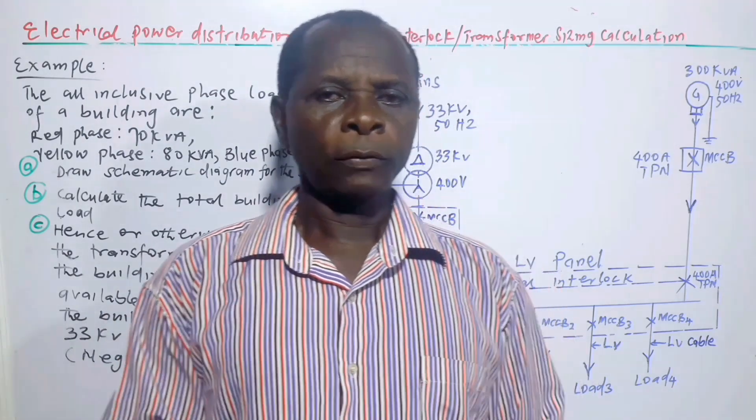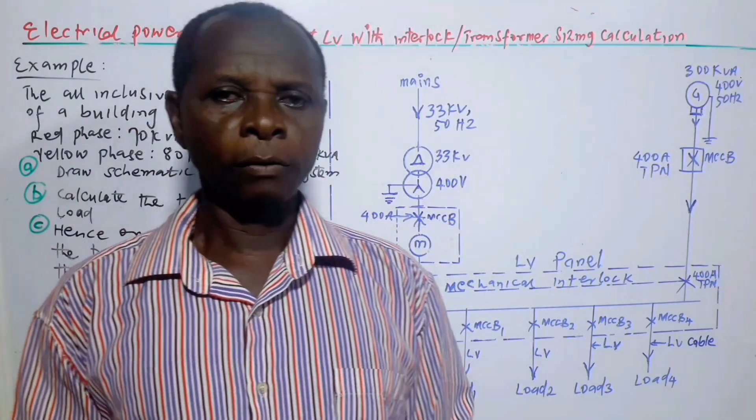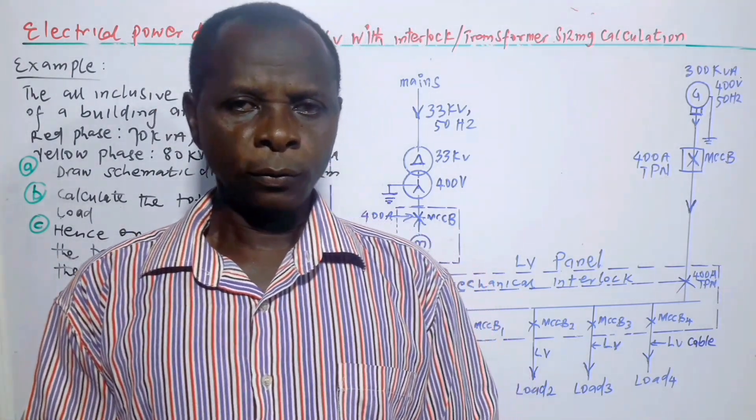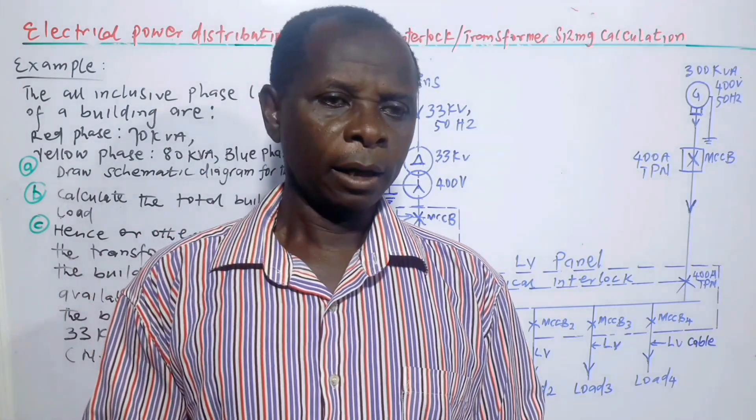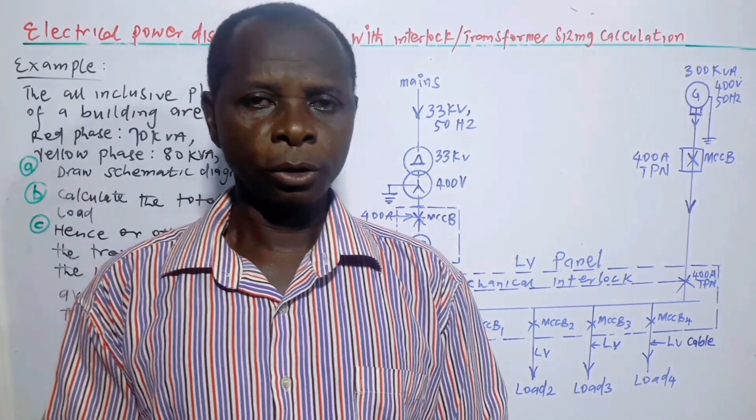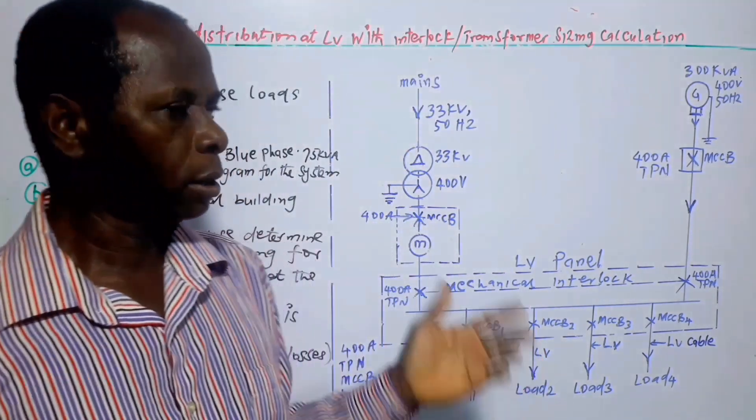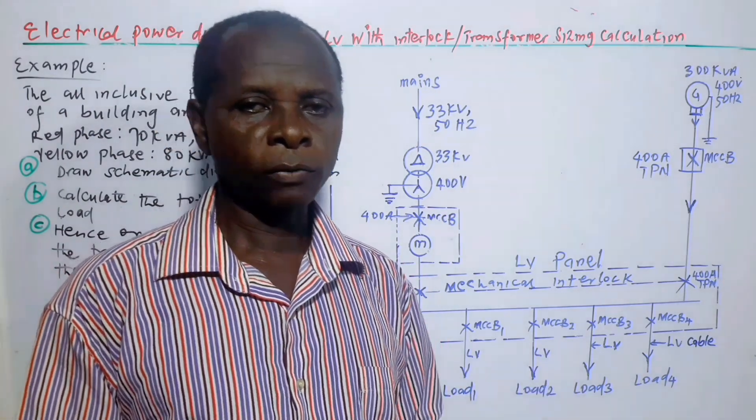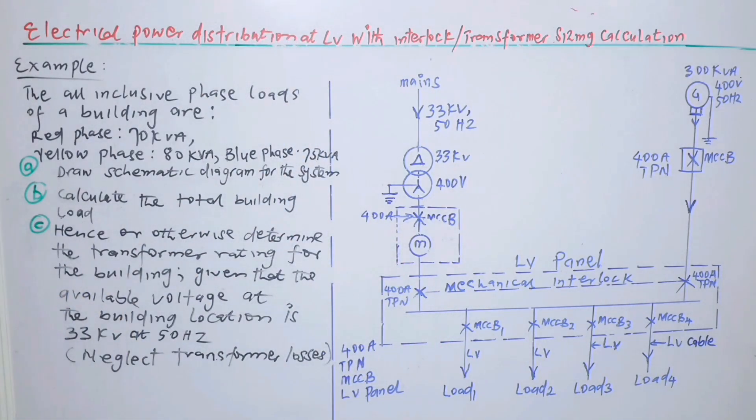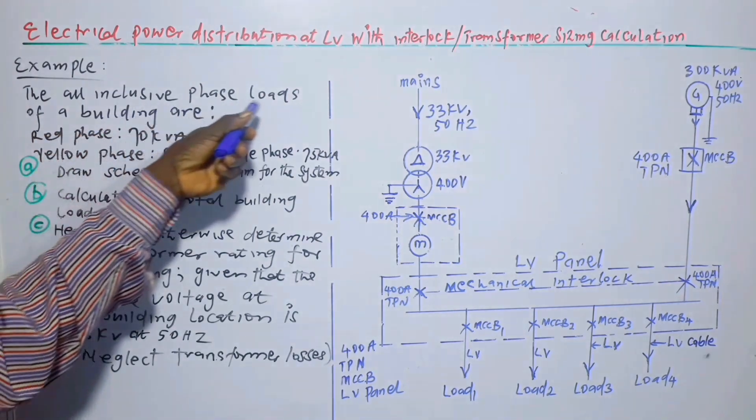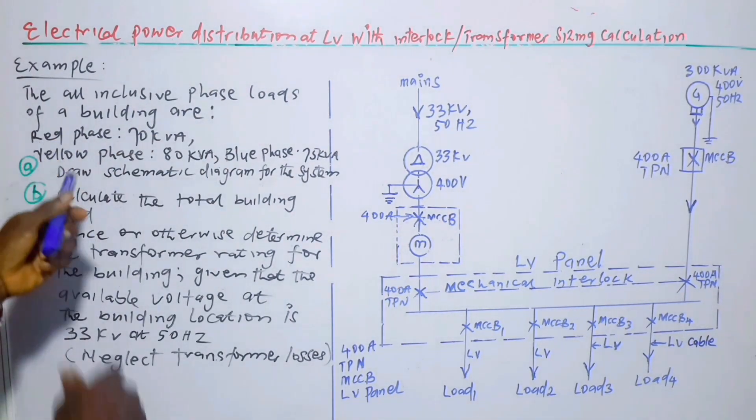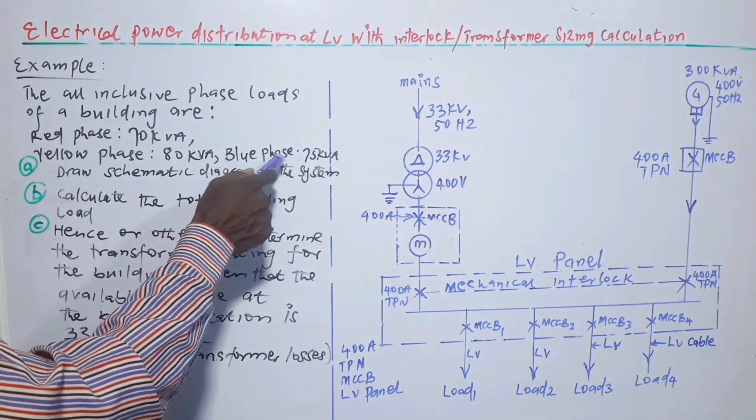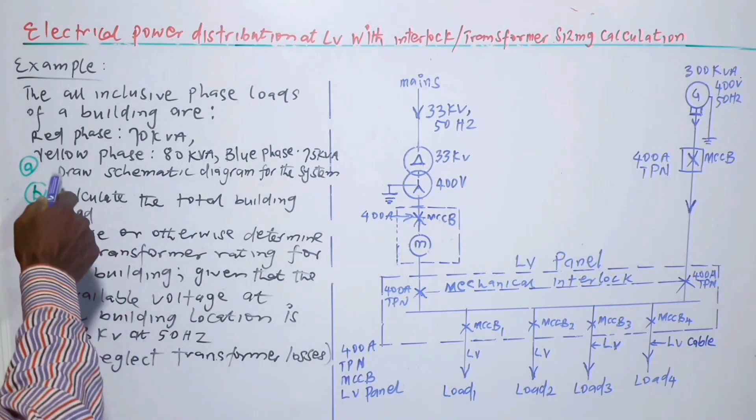For the purpose of a thorough understanding of the concept of a power distribution system at low voltage and transformer sizing calculation, the concept is illustrated making use of an example as follows. Example: the all-inclusive phase loads of a building are red phase 70 kVA, yellow phase 80 kVA, blue phase 75 kVA.